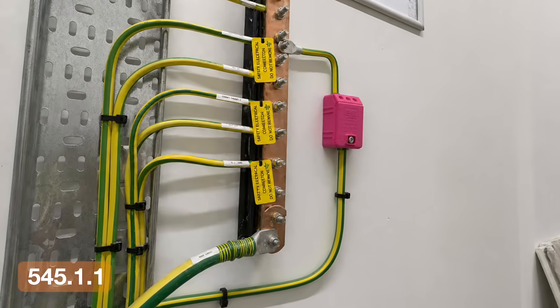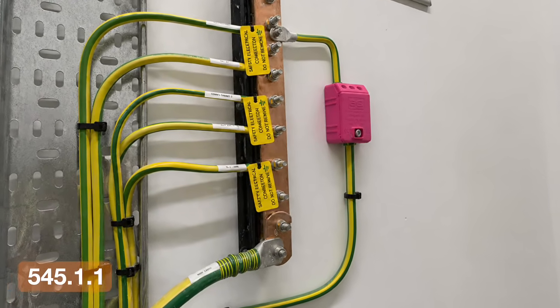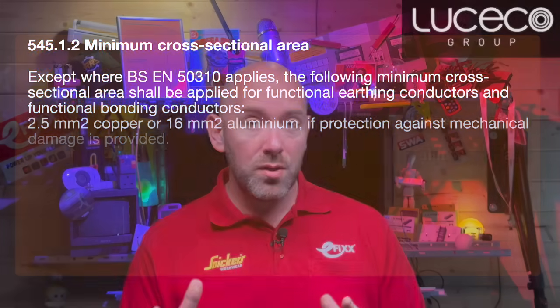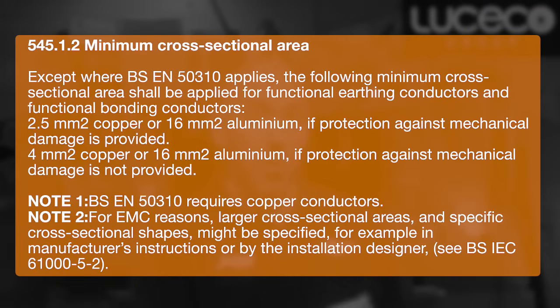Where multiple functional conductors are used, the concept of a main functional earthing terminal is introduced. This provides a single control point of connection back to the main earthing terminal. Sizing is also handled differently. These conductors are not sized based on fault current like a CPC. They are sized based on the expected operational current, taking into account manufacturer's instructions.